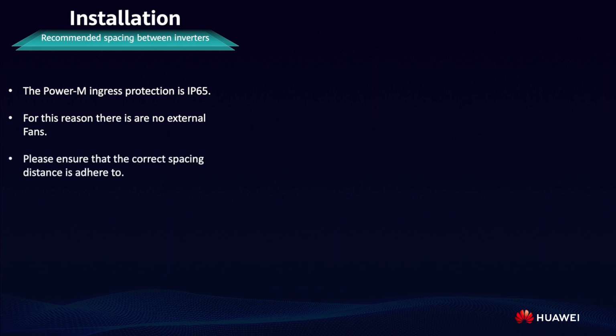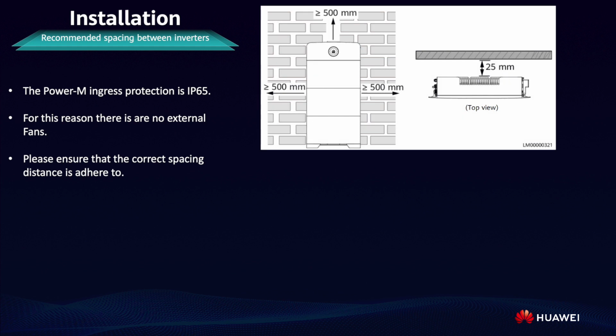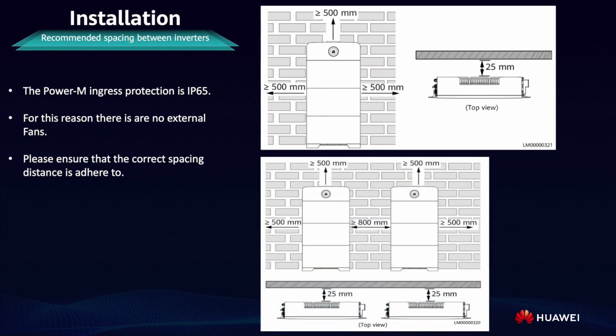Please ensure that the correct spacing distance is adhered to. In the single installation configuration, one will note that a clearance of at least 500 mm is needed and 25 mm from the wall. If more than 2 units are installed, please adhere to at least 800 mm spacing between the 2 power modules and 25 mm from the wall.